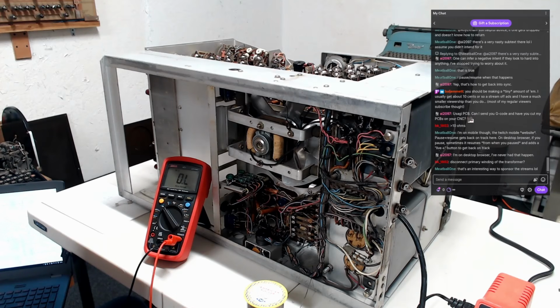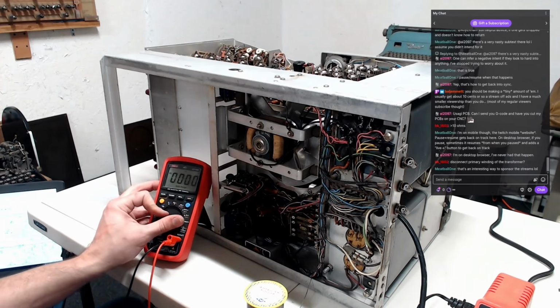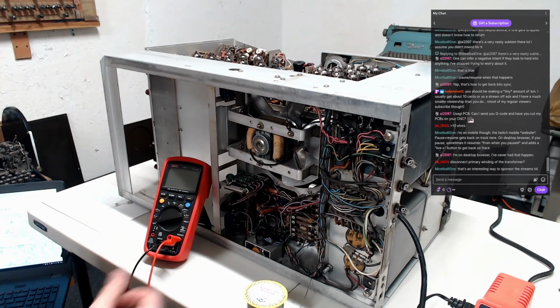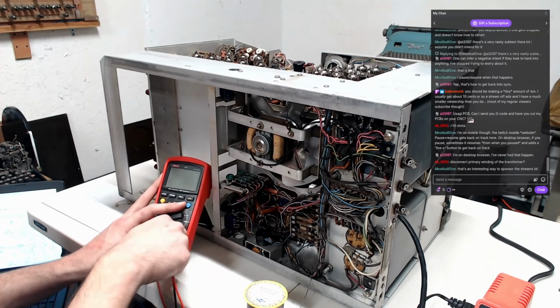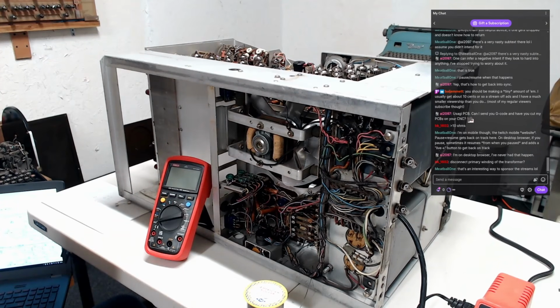That's usually to prevent the plate voltage from being applied until the filaments have had a chance to warm up. Yep, that's exactly what it's for. The other possibility is that the rectifier tubes have separate filament connections. They're diodes, not tubes. Oh, they're solid state, what kind of diodes? The kind that we exploded 4 of them. I've replaced them and they're good, and the rest measure good, or measured good the last time I tried. Were they like selenium or something? No, they're silicon.